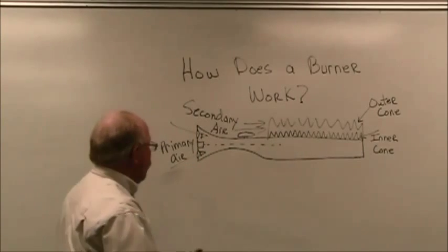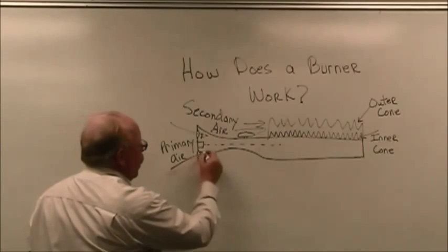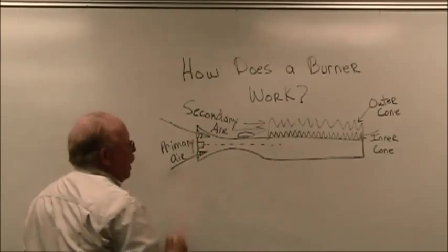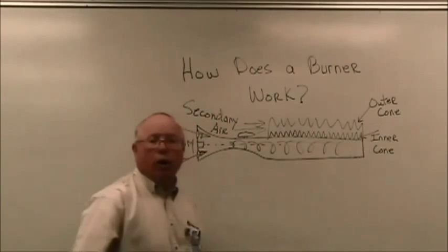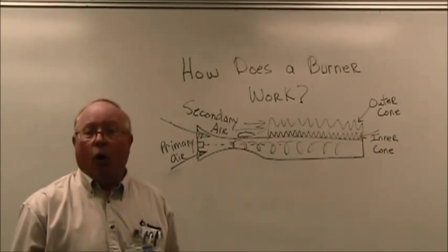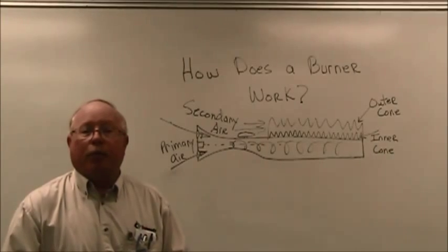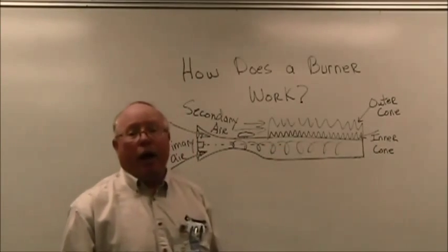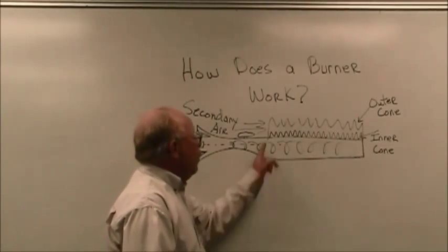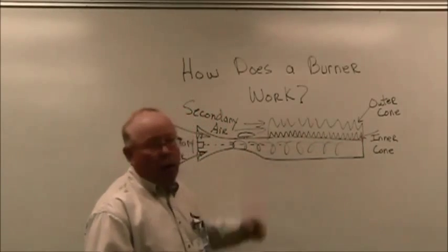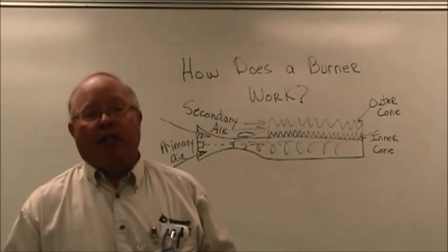This drop in pressure allows for a suction to bring in primary air into and mix with the gas so that we get our first shot of air for the combustion process. But as I said before, the primary air is not enough for complete and total combustion, and we see the gases burning with the primary air in that inner cone. We have to finish off the process.